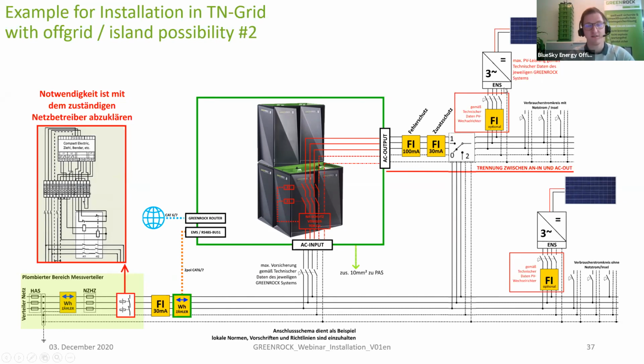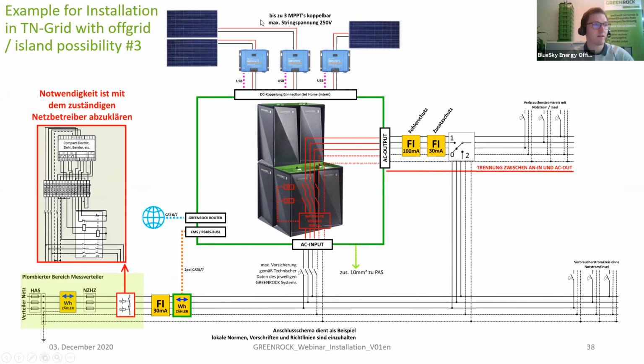That also means the PV inverter will have no grid or voltage to synchronize on. So what we have available here is the so-called DC coupling of the PV modules, because this charger starts as soon as it gets voltage from the PV panels. During the morning hours, they charge up the batteries to a certain point, and as soon as they've reached this point, the AC out is already powered.